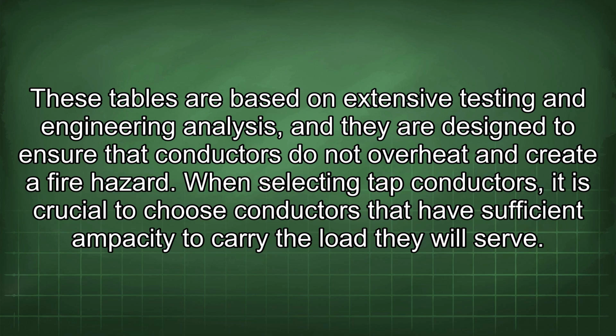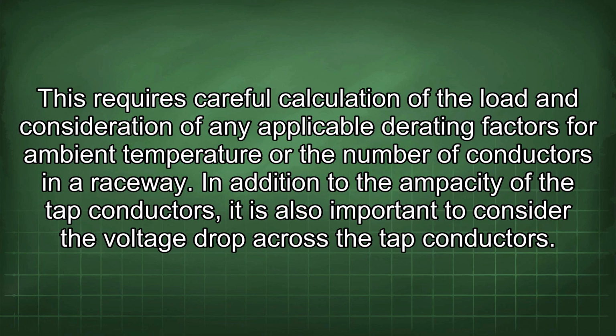When selecting tap conductors, it is crucial to choose conductors that have sufficient ampacity to carry the load they will serve. This requires careful calculation of the load and consideration of any applicable derating factors for ambient temperature or the number of conductors in a raceway.